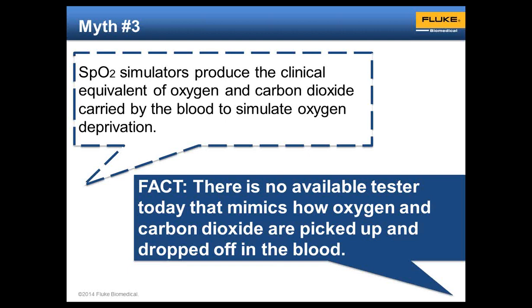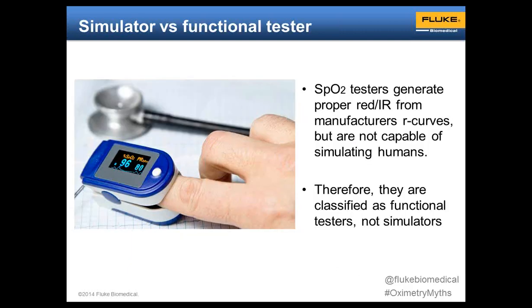When we talk about simulators versus functional testers, what we're talking about is the standard. The 80601-2-61 goes through what's a functional tester and a calibrator. And what we really need to focus on is primary versus transfer standards. So ground truth is where you would start during a clinical trial where you're measuring blood gases. Then we go to indirect measurement, which is the SpO2, and then a tester is one removed from that where we're taking the R curve from the medical device and then simulating that. And that's where the standard actually makes a distinction between a tester and a calibrator. Again, 80601-2-61 is a good source for looking at the differences between those.